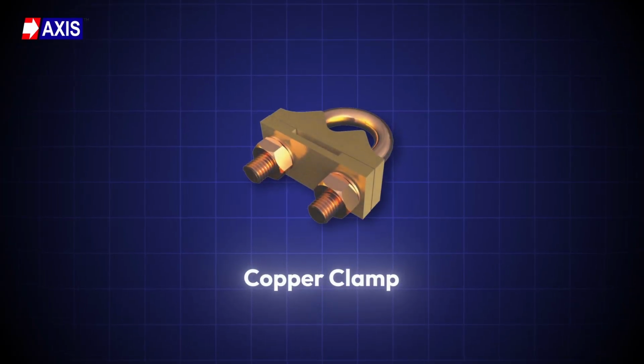It creates a secure connection between the wire and the rod, ensuring good electrical contact. This helps dissipate fault currents safely. However, for equipment earthing, using copper clamps is recommended so it can handle fault currents effectively. But people sometimes go with stainless steel instead of copper. This is fine if it passes the required fault current. If your clamp is not strong enough to handle that, there is a chance it will be destroyed.